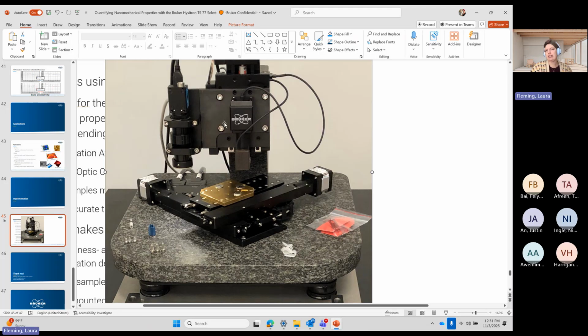The piezo scanner is really delicate. The scanner is what's in charge of moving the transducer over the sample surface during imaging, which means it is 5 different piezos. There's a Z ring piezo that extends and retracts to move the tip up and down, and then there are XY quadrant piezos. Piezos don't really like being curved. It's hard on them. They're extremely fragile, and any lateral force to the end of that piezo dovetail can cause damage and can cause it to break.